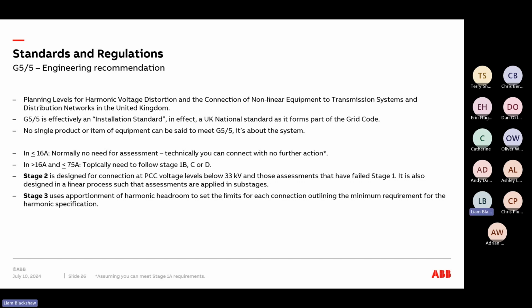If we're adding, let's say, something that has a low load, something that's less than or equal to 16 amps, in a lot of cases there's no need for an assessment. Technically, you can connect without any further action, assuming you can meet what they class as the stage 1A requirements. But if it's greater than 16 or less than 75 amps, then you typically need to follow either stages 1B, C, or D.